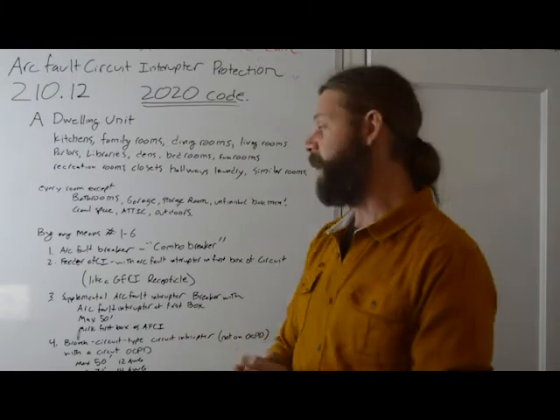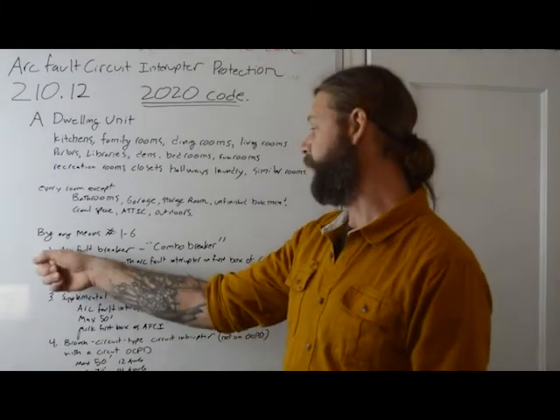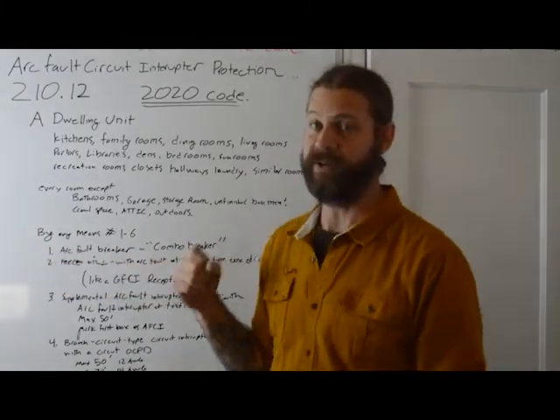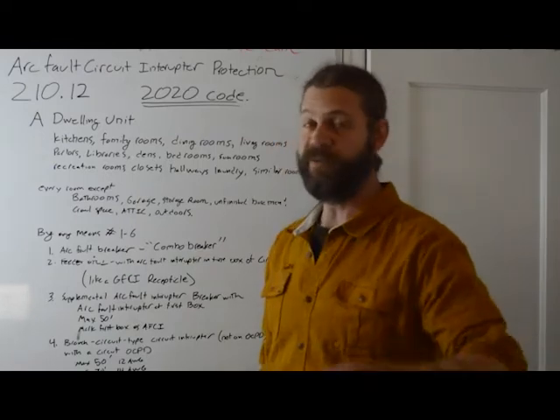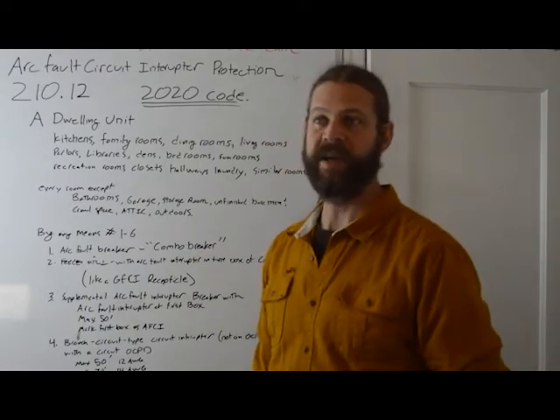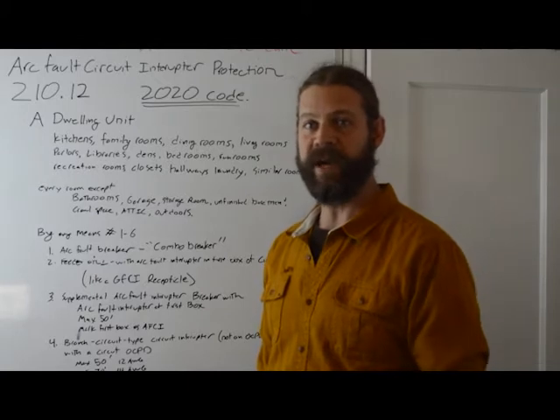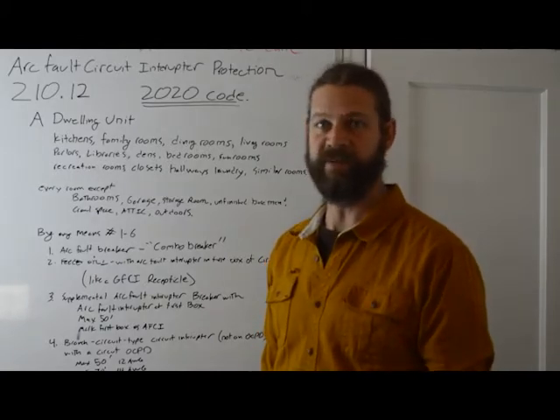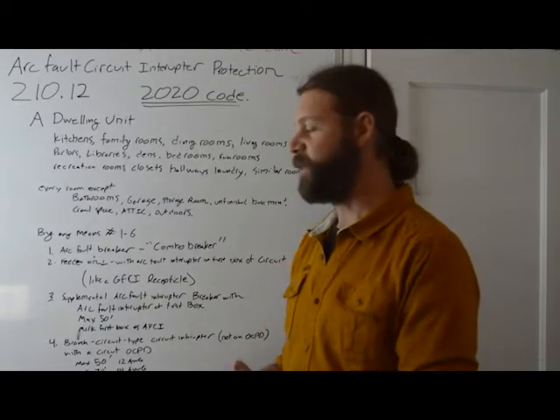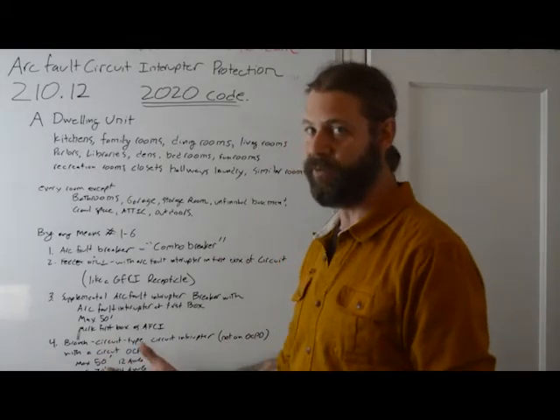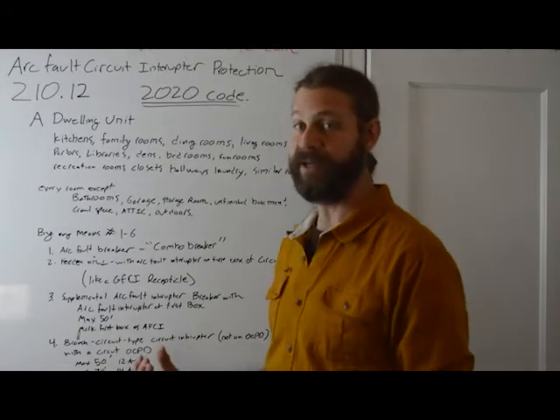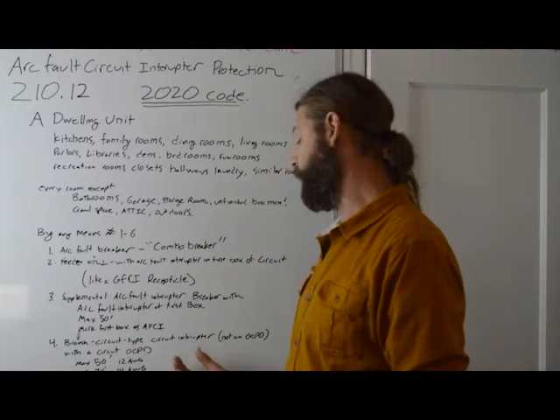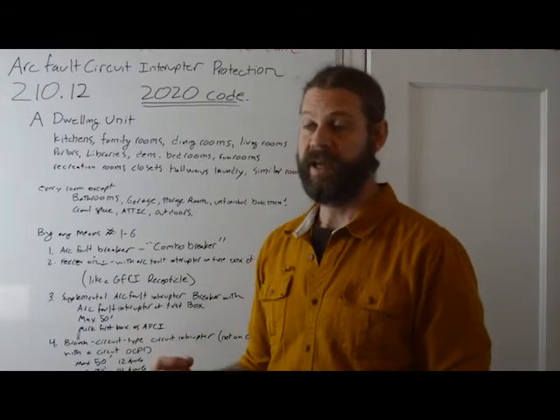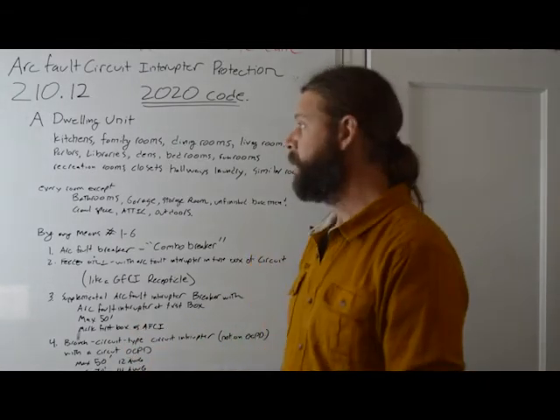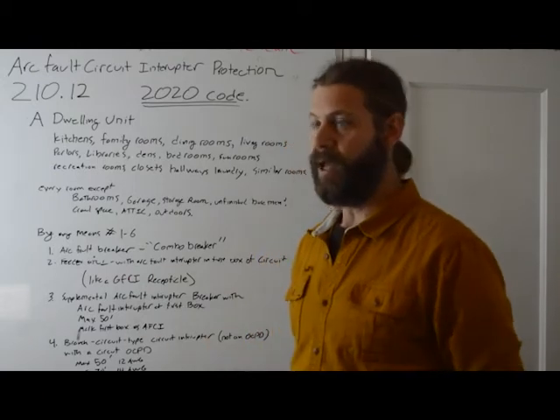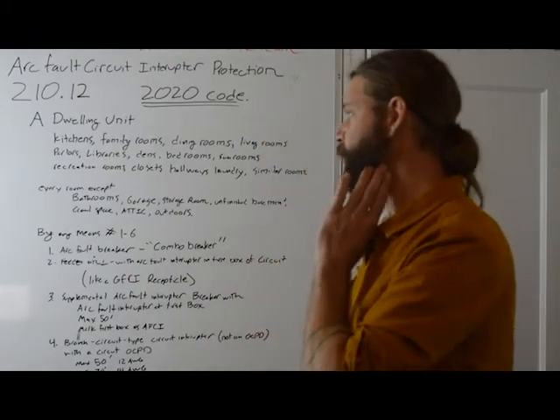And the easiest way to do that by far is with one of these combination arc fault circuit breakers. But if you are doing an upgrade to an old house with like a very old Zinsco panel, or, God forbid, a fuse box, it is possible to install a combination of overcurrent protection devices and arc fault circuit interrupters that will meet code requirement. You could do that. It's possible.